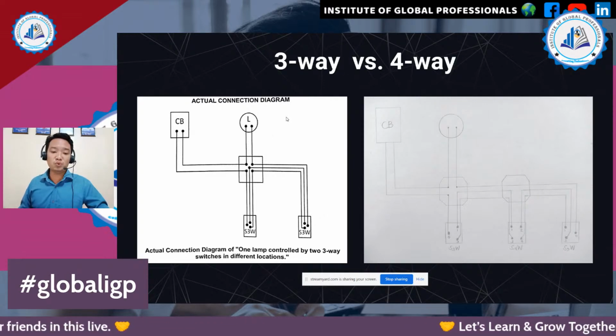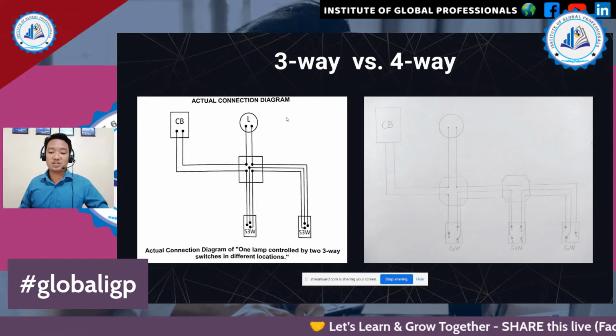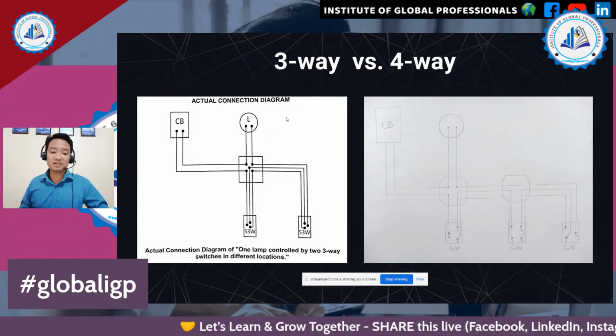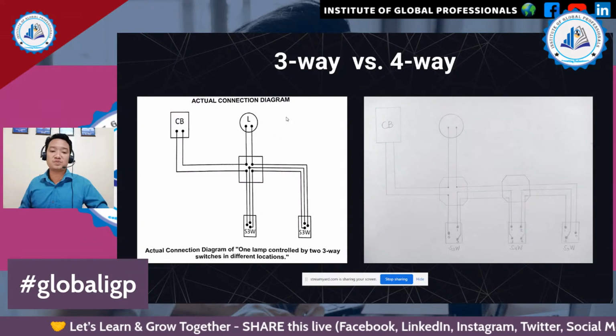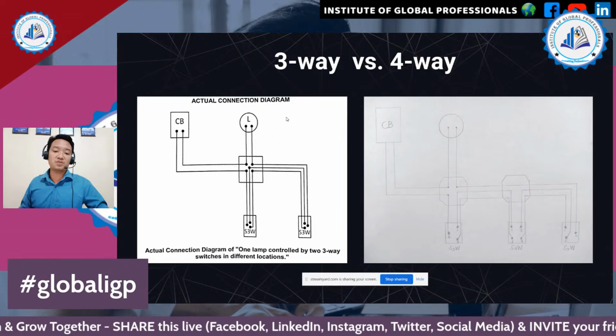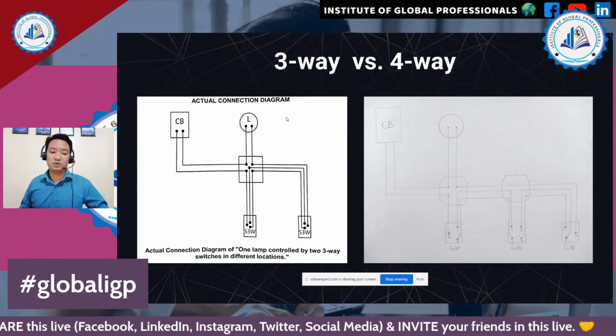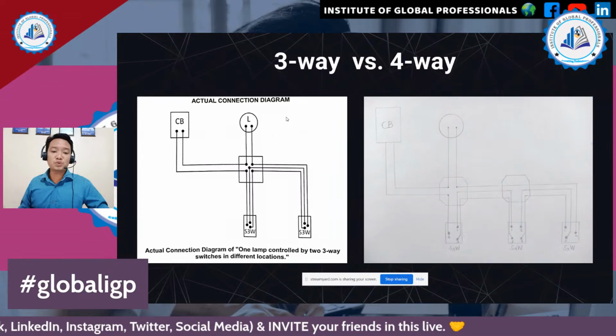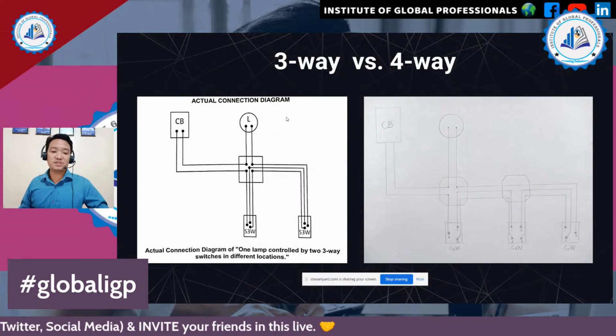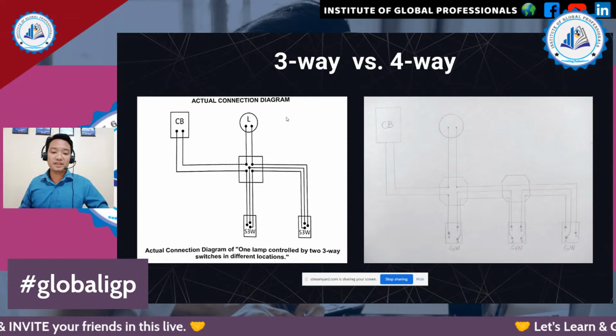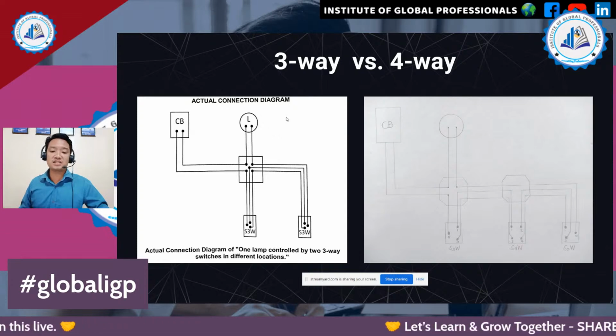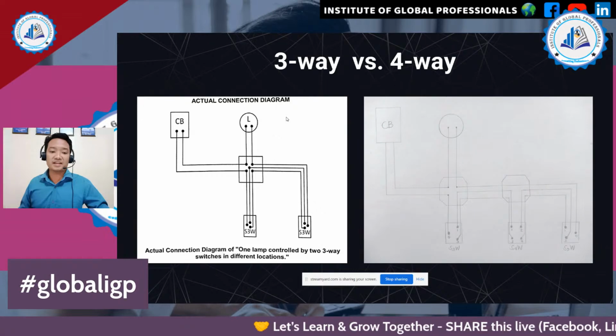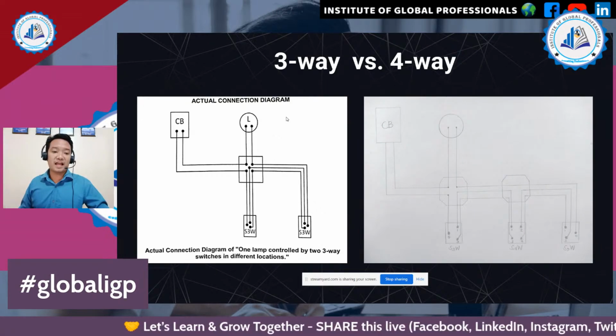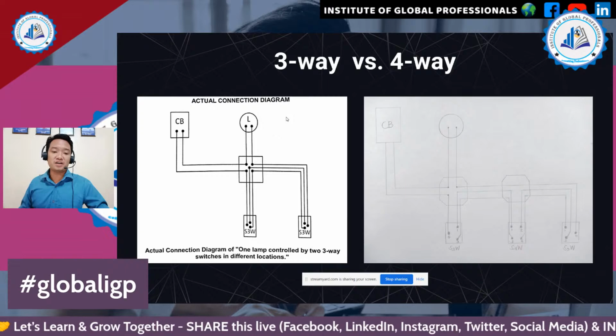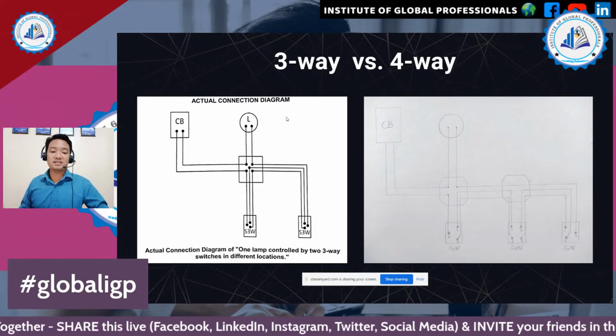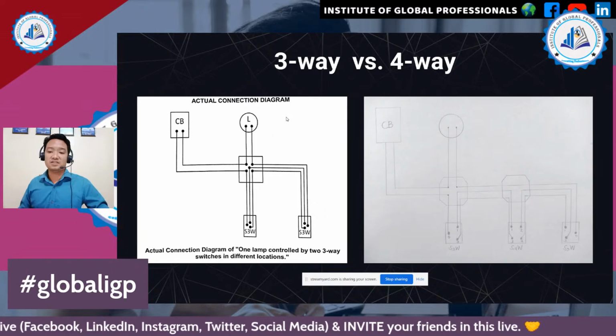And we have two travelers connected with each other, wherein terminal 1 is connected to terminal 1 of the other S3W, and terminal 3 to terminal 3 of the other S3W. We also have the neutral wire connected from the circuit breaker to the lamp, and then from the lamp to the zero common terminal of the S3W. In the second line, we have the circuit breaker directly connected to the S3W common terminal 0.